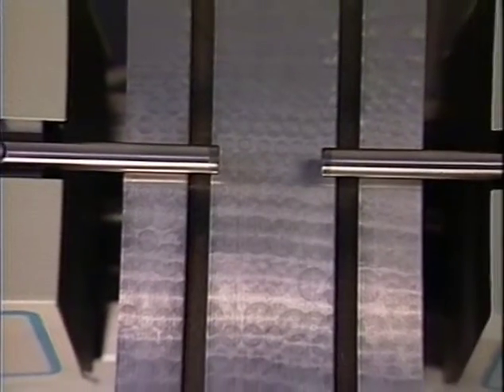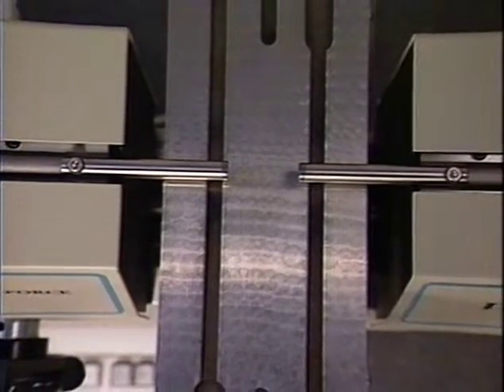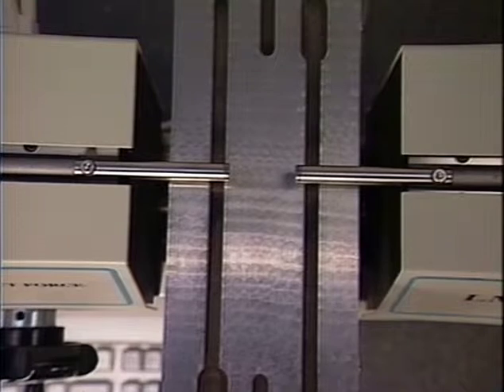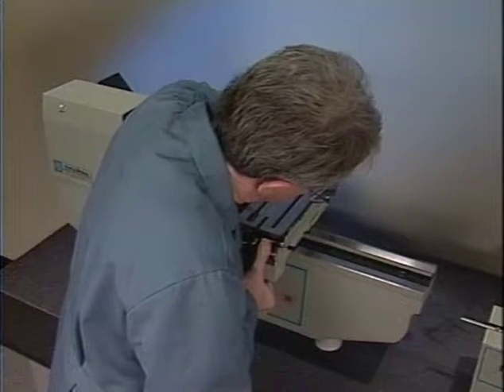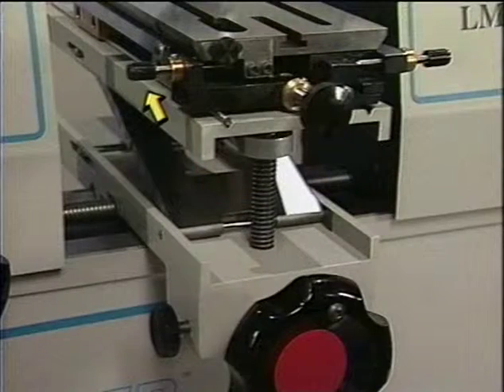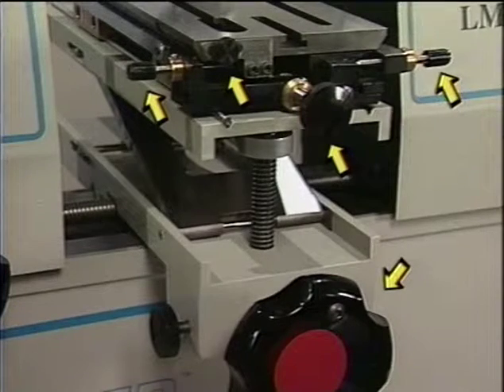The LabMic's large measuring table with integrated slots for fixtures and clamps makes gauge or part alignment fast. LabMic's single-axis table is standard with the machine. The optional five-axis table is used for more demanding part alignment. Its swivel, floating, centering, tilt, and elevation adjustments are simple to do.